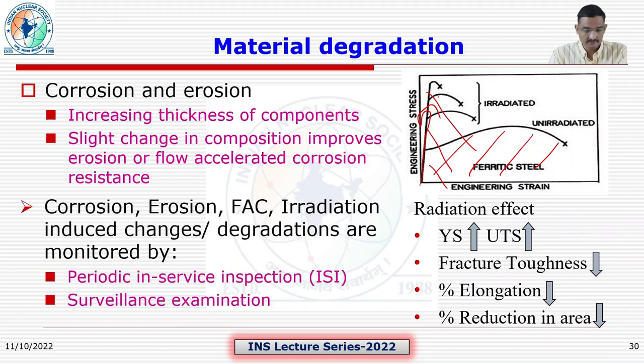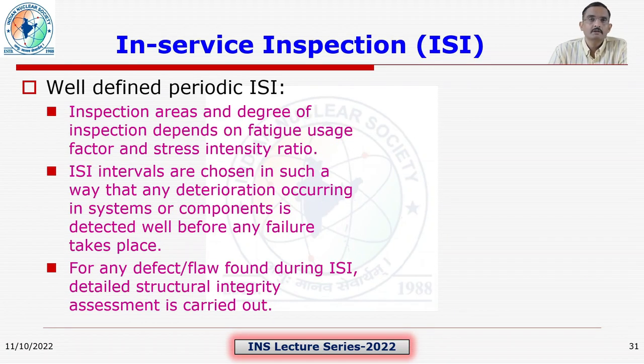Corrosion, erosion, flow accelerated corrosion, and irradiation induced degradations are monitored in nuclear power plants by periodic in-service inspection and a well-defined surveillance program. This in-service inspection covers all critical items important to safety as per IAEA safety guide 50-SG-O2. Inspection areas and degree of inspection depend on fatigue usage factor and stress intensity ratio. In-service inspection intervals are chosen so that any deterioration occurring in systems or components is detected well before any failure takes place.